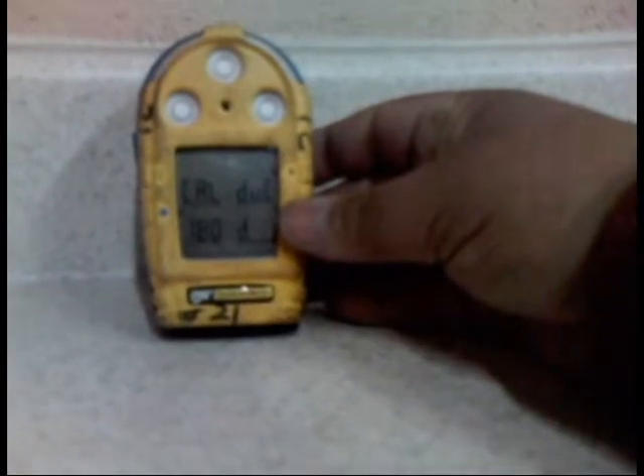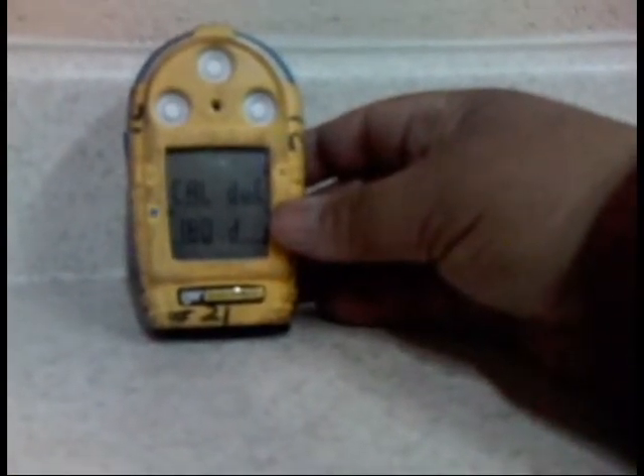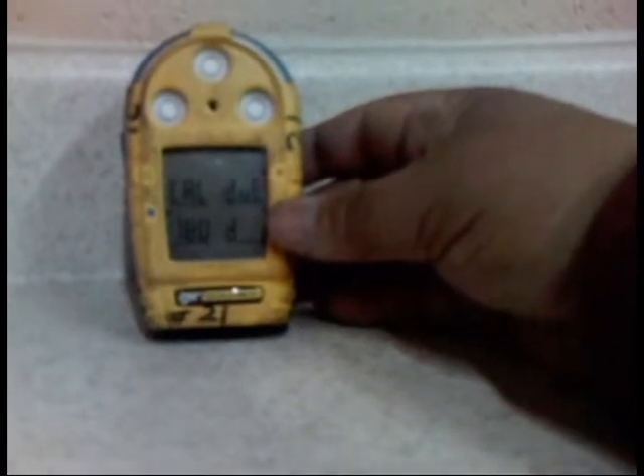Now we are going to allow the unit to go ahead and finish its cycling and programming. As I stated, the book shows steps 4 and 5 to change alarm set points. We do not wish to do that. We're going to go ahead and let the unit create its own set points. This step can also take a couple of minutes. All right, then it comes up with calibration due 180 days, showing we have a successful calibration. And you are ready to use your sniffer.